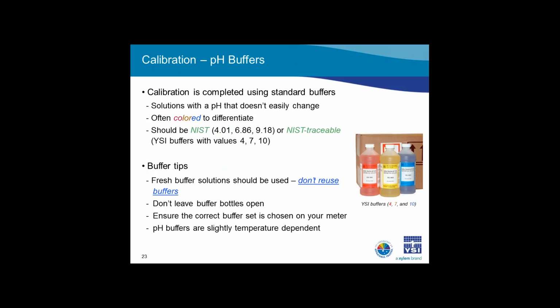Now that we covered what the calibration is actually doing to the system, and the importance of also measuring temperature, let's talk about what you can do to ensure you are calibrating your system properly. First, make sure you are using fresh, traceable pH buffers. At YSI, we recommend using traceable buffers to guarantee you are using a highly accurate solution. We don't want to introduce error to the system just by using an inaccurate solution for calibration. That would introduce error before we even got started.